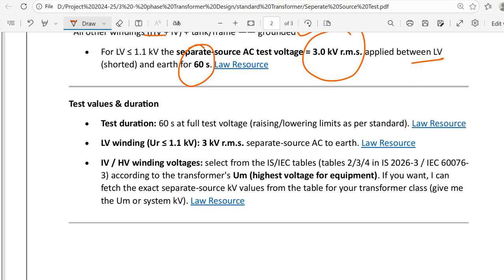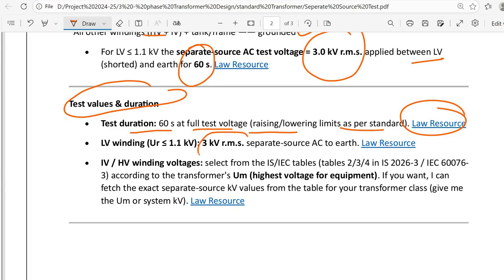Now the test values and durations. Test duration is 60 seconds at full test voltage, with rising and lowering limits as per standards. And for LV winding, if less than 1.1 kV, it is 3 kV RMS.